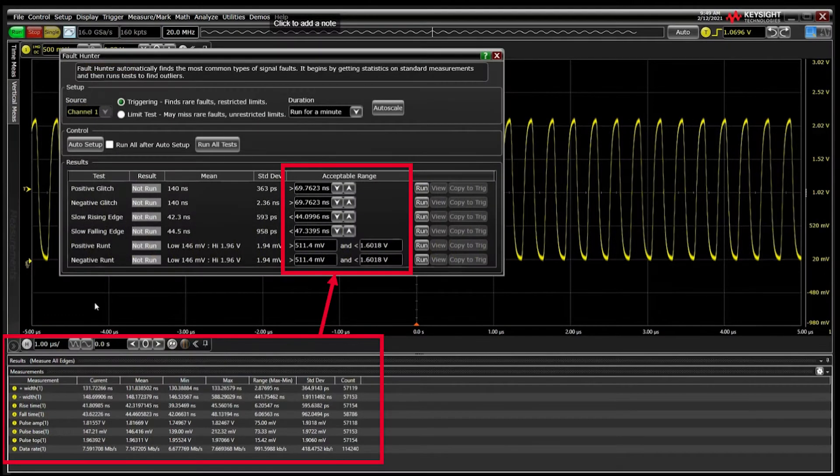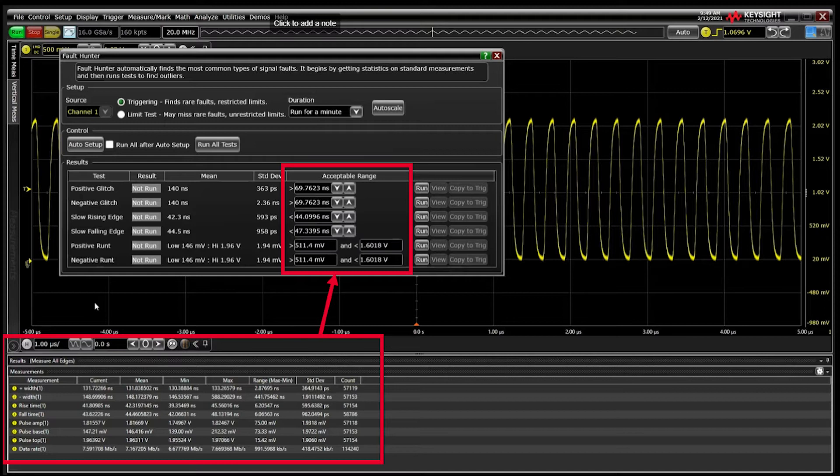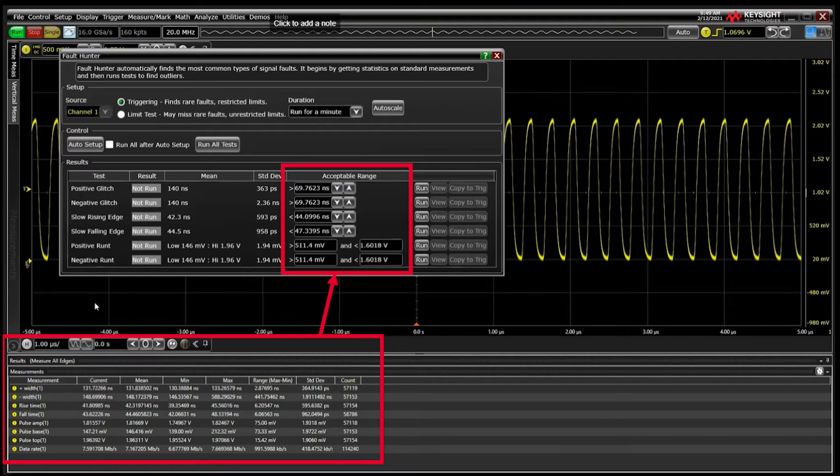The Auto Setup takes about 30 seconds and uses automatic measurements to create acceptable ranges used to identify glitches, slow edge speeds, and runs.